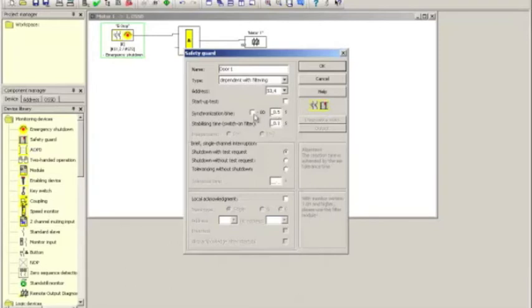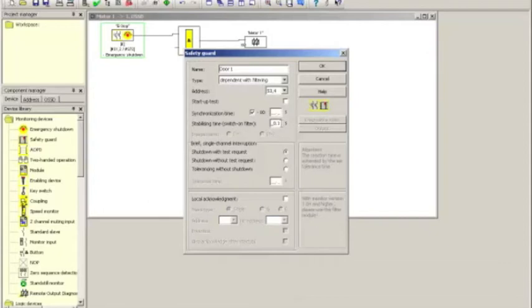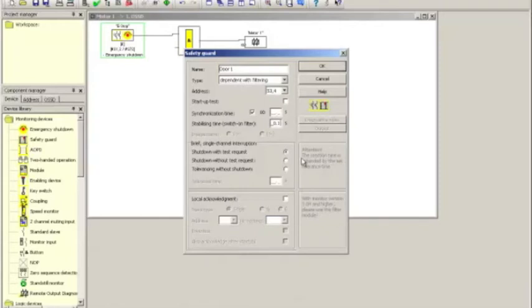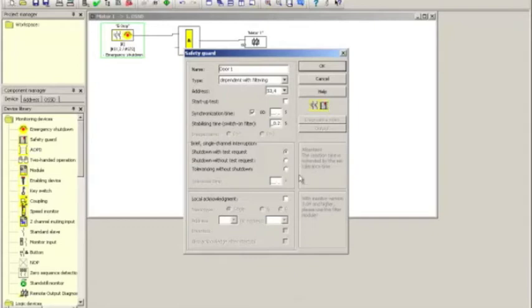It has no bearing whatsoever on the safety part since we're dealing, in this case, with the way the system will start up. It will, of course, immediately shut down as soon as one contact opens up, when the doors open. Also, experience taught me that doors tend to be bouncy, and I want to add a little more stabilization time, giving the contacts more time to settle into their closed state. So, I will utilize 0.2 seconds as my stabilizing time. That's all. In this case, I do not select a local acknowledgement because I want this magnetic door switch to auto-start as soon as the door is closed.